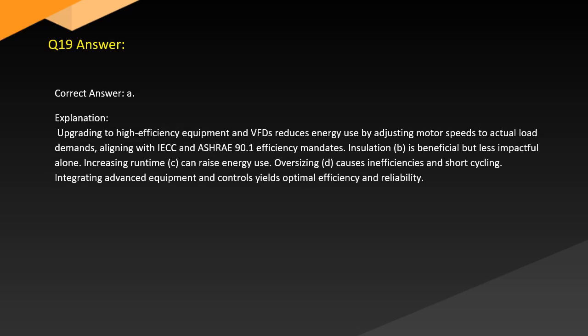Answer. Correct answer: A. Explanation: Upgrading to high-efficiency equipment and VFDs reduces energy use by adjusting motor speeds to actual load demands, aligning with ASHRAE 90.1 efficiency mandates. Insulation, B, is beneficial but less impactful alone. Increasing runtime, C, can raise energy use. Oversizing, D, causes inefficiencies and short cycling. Integrating advanced equipment and controls yields optimal efficiency and reliability.